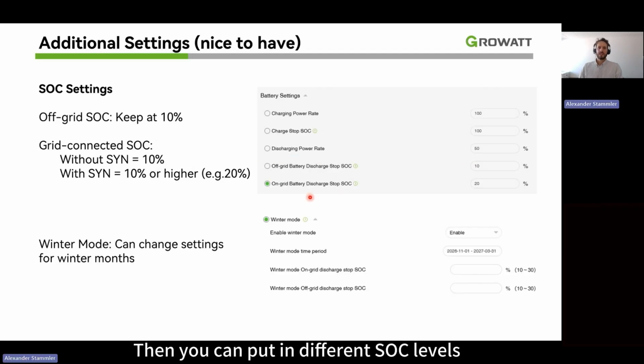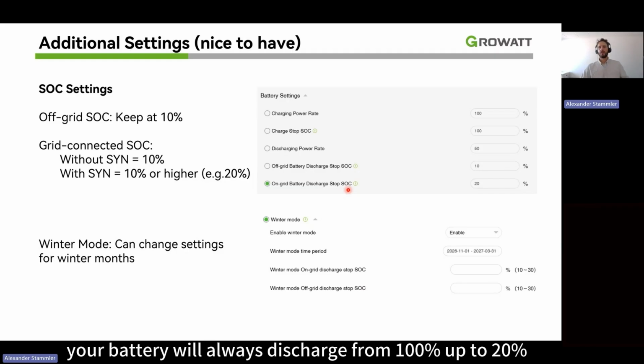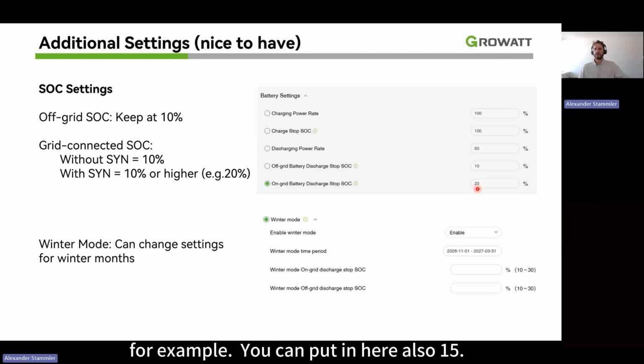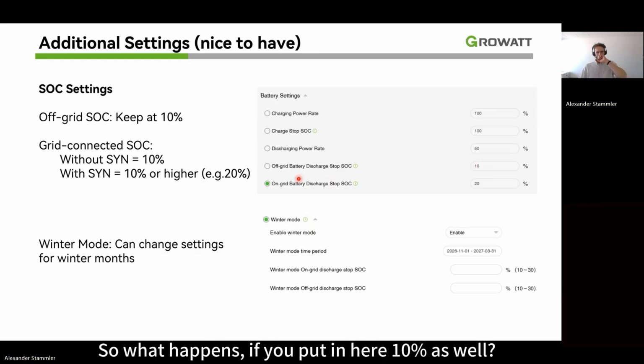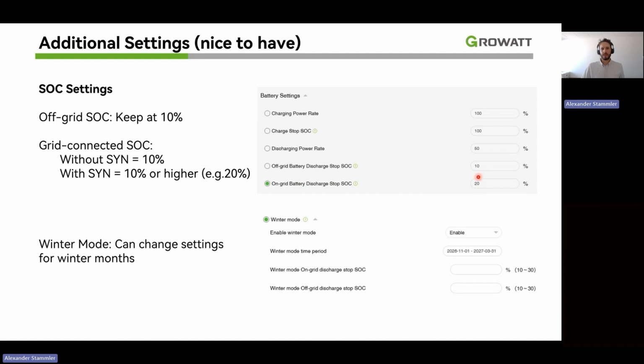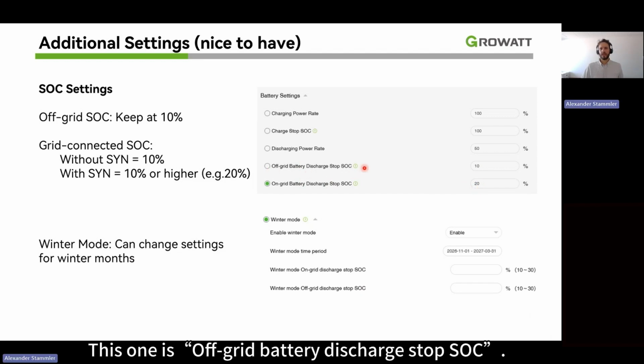Then you can put in different SOC levels, which is important for the backup system. So you can here put, for example, on-grid battery discharge stop SOC. This means in a normal situation where you still have grid power, your battery will always discharge from 100% down to 20%, for example. You can put in here also 15. The minimum is 10%. So what happens if you put in here 10% as well? This one is off-grid battery discharge stop SOC.